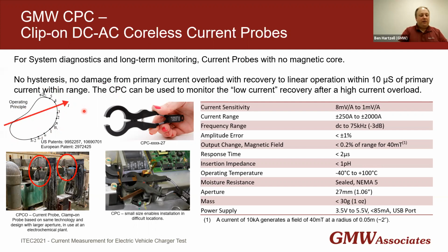The CPC clip-on current probe and the related CPCO clamp-on current probe are designed with the idea that Ampere's circuital law can be approximated with many individual magnetic sensors along a curve outside the conductor, and rather than integrating the continuous curve, we do a summation of the magnetic field at these points around the curve instead. This, in combination with several other tricks, gives an approximate but still quite good measurement of the current within the curve while rejecting magnetic fields and currents outside the curve. Again, for more detail on the operating principle, please see Ian Walker's presentation.